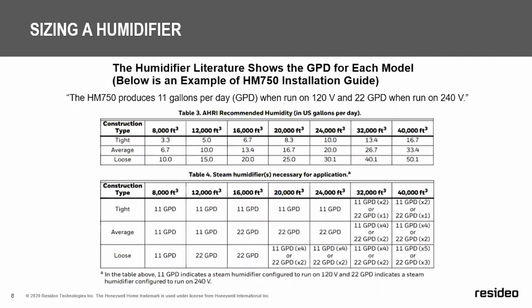This screen shows you the recommended humidity needs in gallons per day of a tight, average, or loose home based on the cubic footage of that home. And below that, you will see the chart for the Resideo steam humidifier and the output of the humidifier and size needed to manage that cubic footage of space. One rule of thumb to consider: as homes get larger, if you have multiple heating systems in the home, you will need multiple humidifiers. It's basic common sense, in my opinion, that if your home is so large that to have the proper amount of heat capacity you need 2 systems, then for the proper amount of humidity, you need 2 humidifiers.